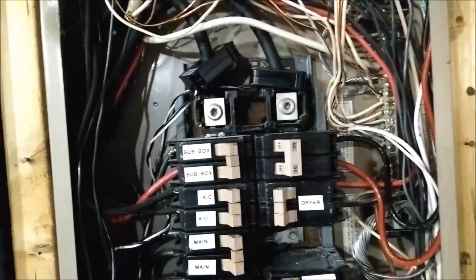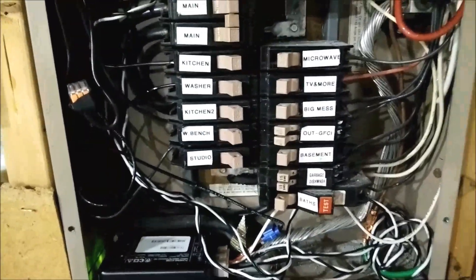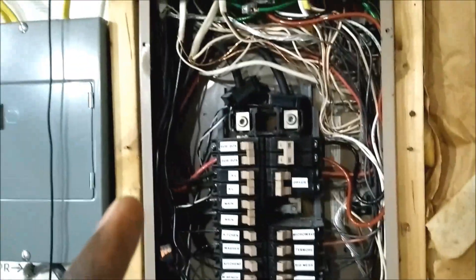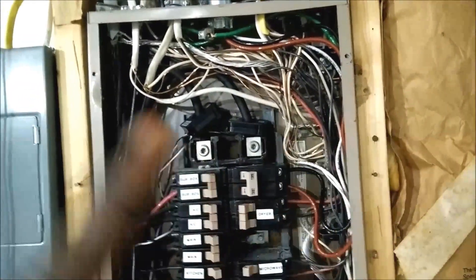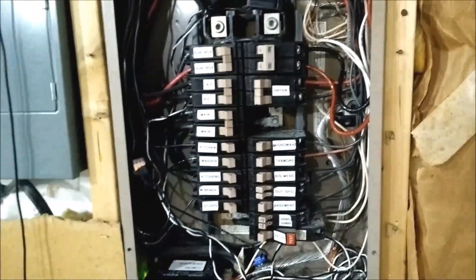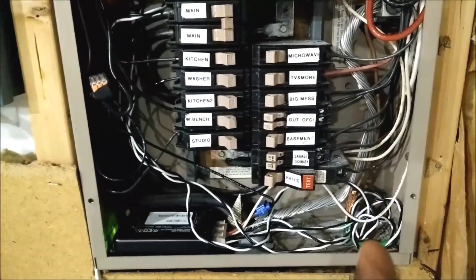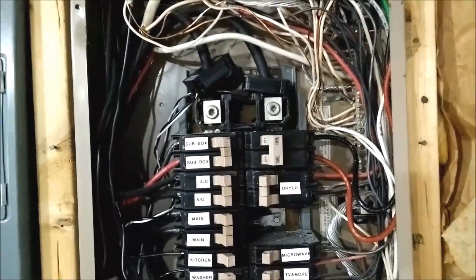The electrician has done a good job with proper grounding, neutral, hots, and the breaker — overall it's a pretty good job. A couple of concerns: my panel is well-organized with wires routed neatly along the corners, neutrals one way and hots the other. It was a pretty clean panel until these extra wires started popping up all over the place. The electrician didn't bother routing them properly — he just clumped them down here. You could easily shorten them, but he just shoved it all in there.